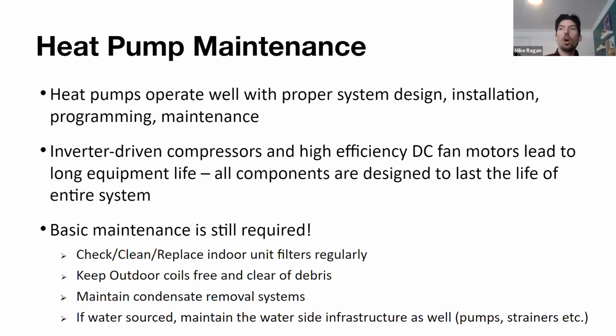The way that all manufacturers' warranties work for heat pump technology and heat pump systems and VRF systems is that we want to make sure that the person who designed the system is trained up and understands how the system is designed. We want to make sure the person who installs the system is also trained up and knows how to properly install the equipment. And lastly, we want to verify that the installation as it's installed matches the design.